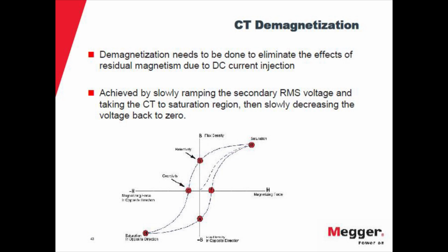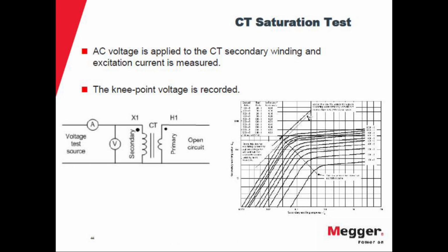So traditionally this was performed with a battery or with a DC current source, but you have to switch the leads, and it was kind of a cumbersome procedure. So after you do that, then you perform the AC test in which you apply the voltage to the secondary terminals of the CT, and you increase the voltage until you find the saturation point, and you get this curve that shows when the CT is not going to be effective anymore.